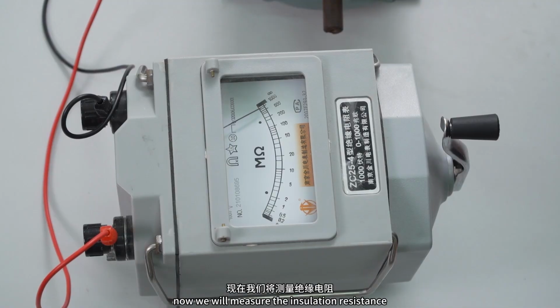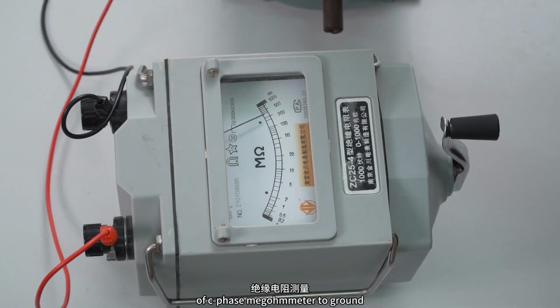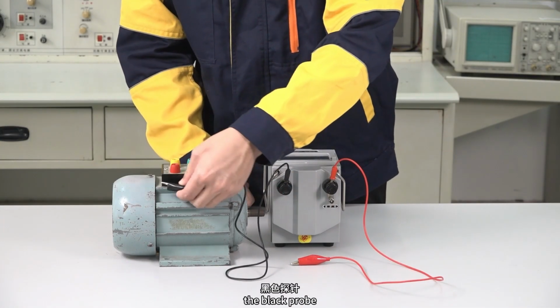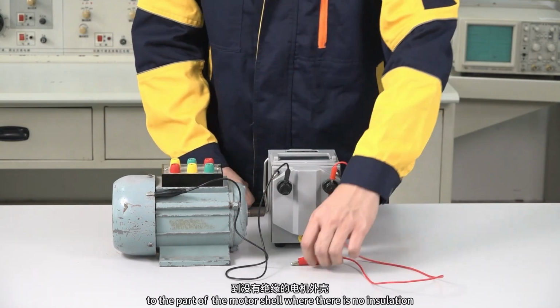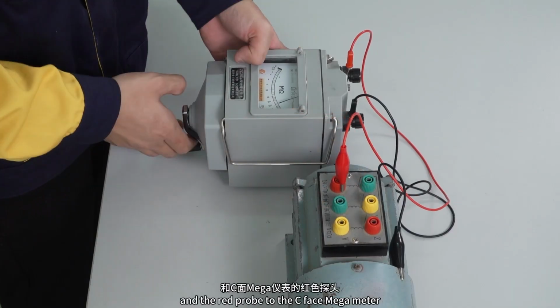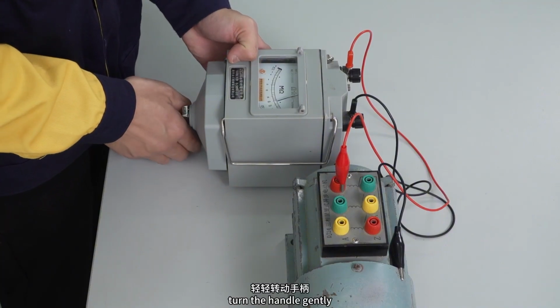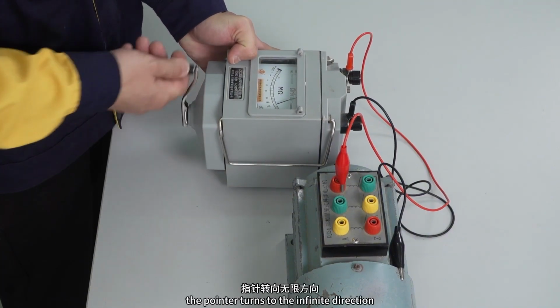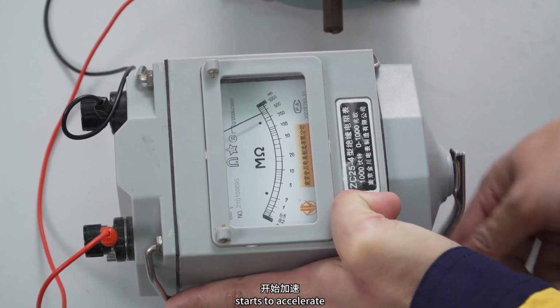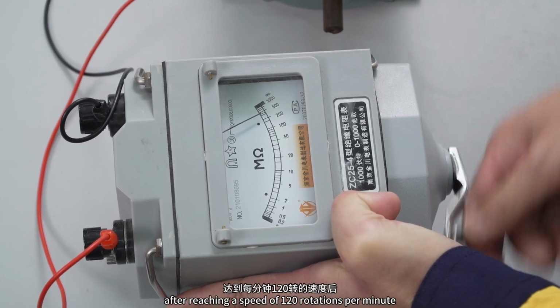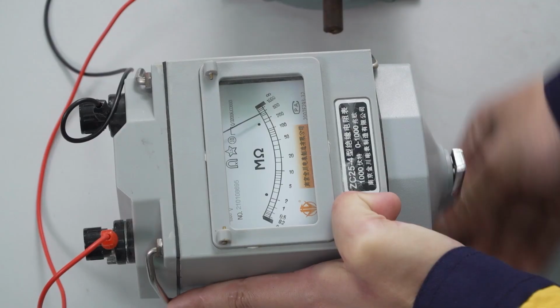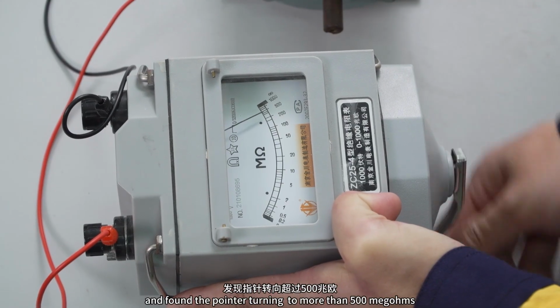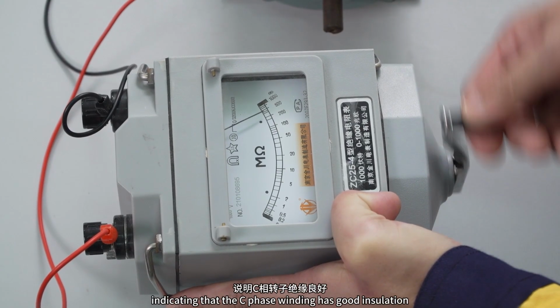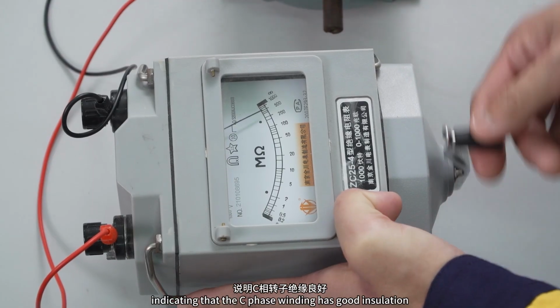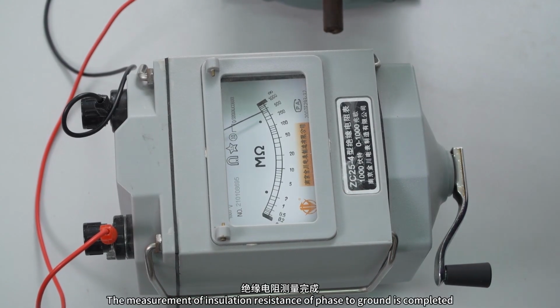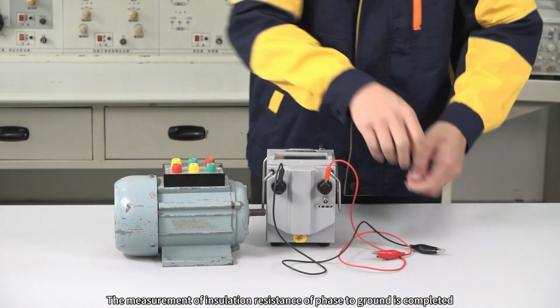Now we will measure the insulation resistance of C phase to ground. When measuring, the black probe is clamped to the part of the motor shell where there is no insulation, and the red probe to the C phase. Turn the handle gently. The pointer turns in the infinite direction. Start to accelerate. After reaching a speed of 120 revolutions per minute, the pointer turns to more than 500 megohms, indicating that the C phase winding has good insulation. Slowly stop. The measurement of insulation resistance of phase to ground is completed.